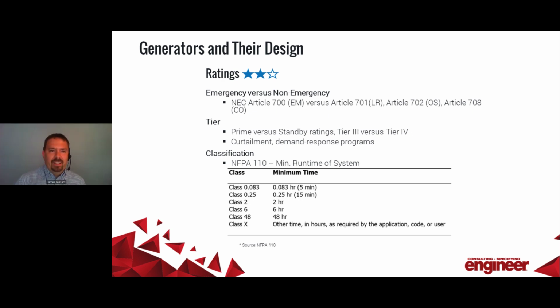Absolutely, that's great feedback. So as we get into generators further, we want to make sure that we understand what the ratings of the generators are. It's important on every project that we define the ratings of the generator specific to your project. First and foremost, NEC sets up an emergency versus a non-emergency classification. If it's serving an NEC Article 700 load, typically, those are egress lighting, exit signs, fire alarm, those types of loads. Very specific. The NEC defines what loads fall into which article. So that's emergency versus non-emergency.